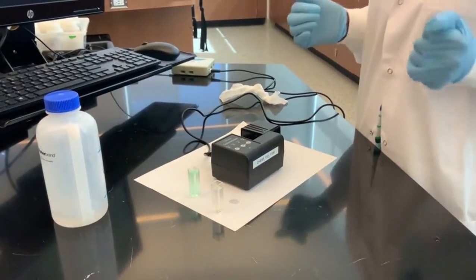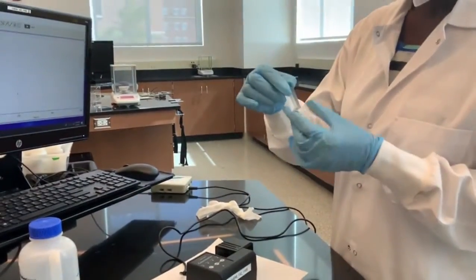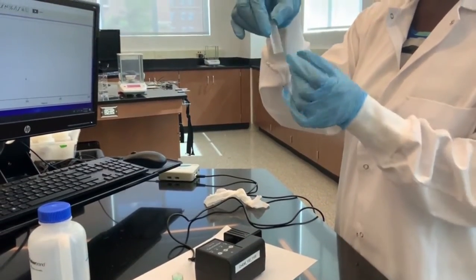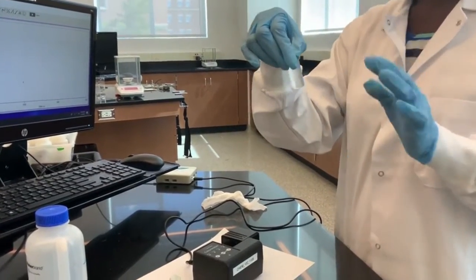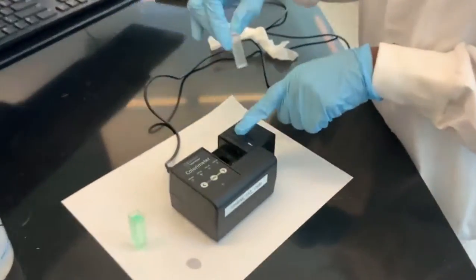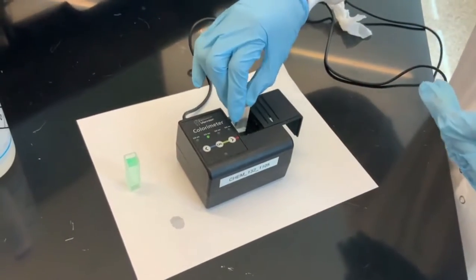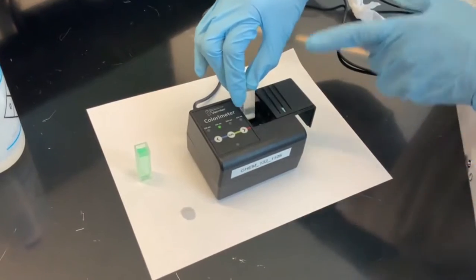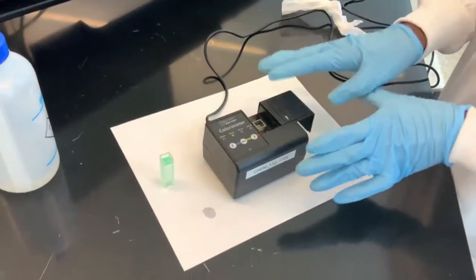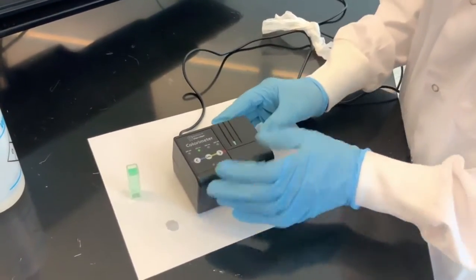In order to calibrate our colorimeter, we're going to use distilled water in a cuvette. It's very important to know that before you place the cuvette, it has a clear part and some opaque part, a part that's not that clear. So if you look at your colorimeter, you look at an arrow. Where the arrow is pointing, where the light is passing through, you place the clear part directly there.